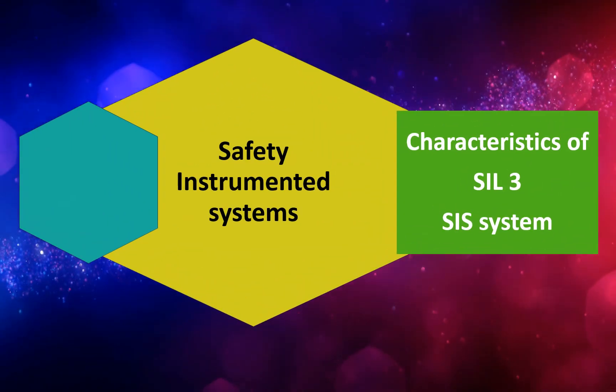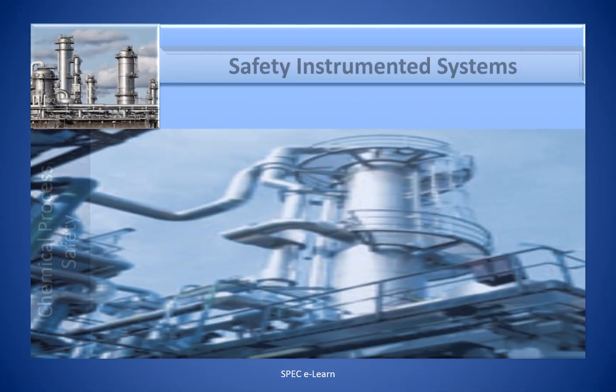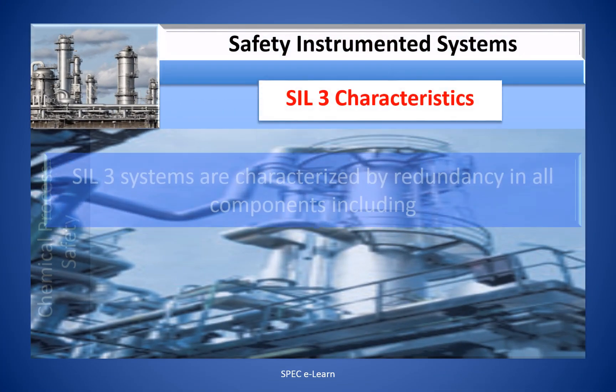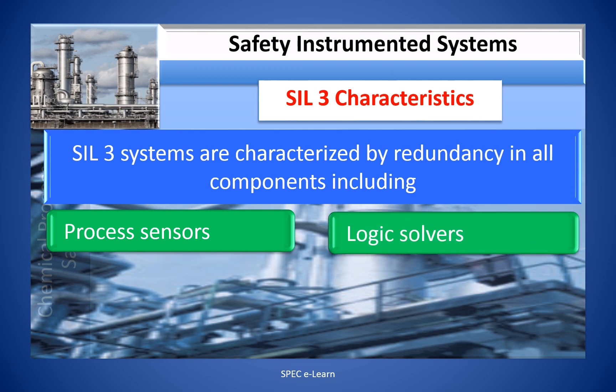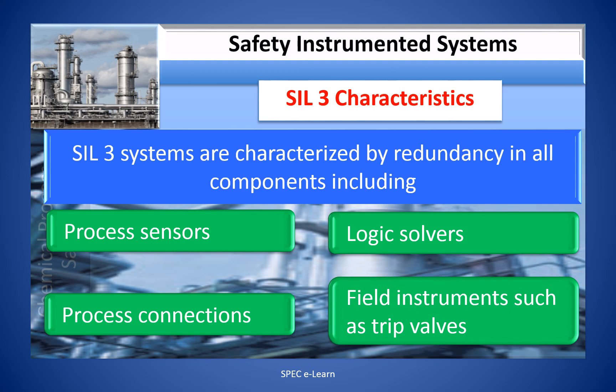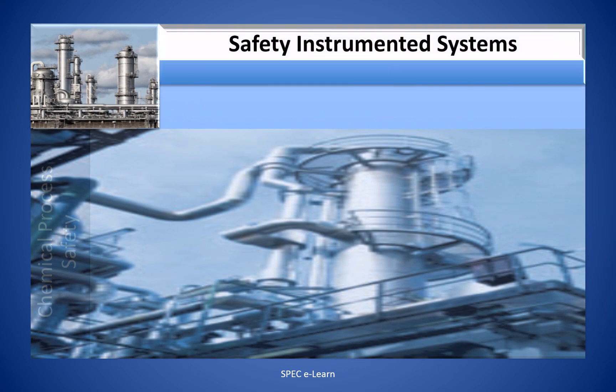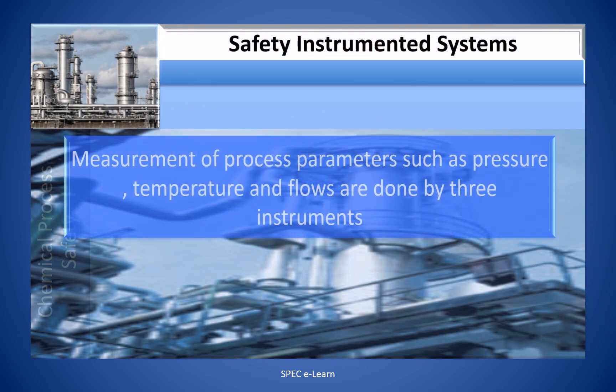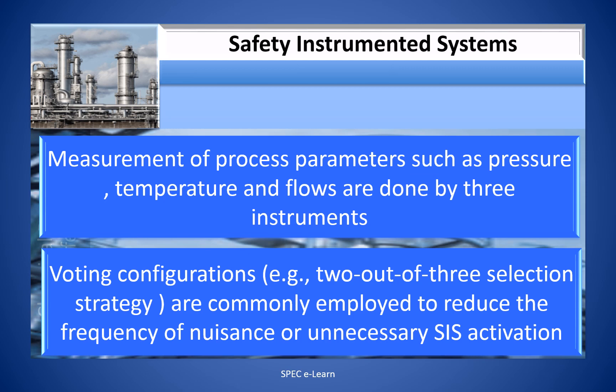Characteristics of SIL 3 SIS systems. SIL 3 systems are characterized by redundancy in all components, including process sensors, logic solvers, process connections, and field instruments such as TRIP valves. Measurement of process parameters such as pressure, temperature, and flow are done by three instruments using voting configurations.